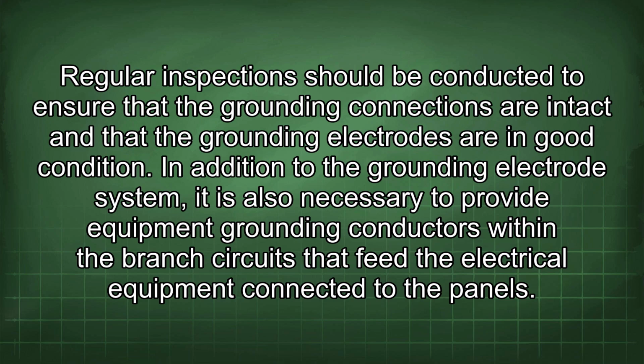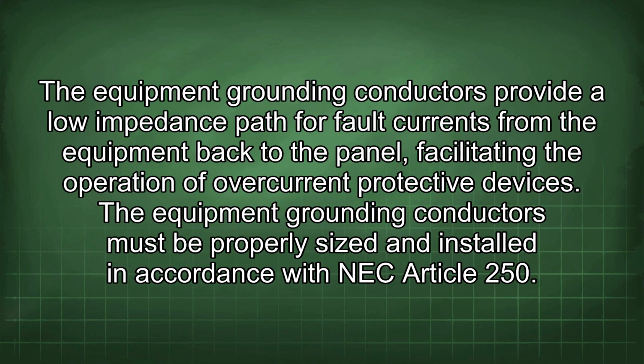In addition to the grounding electrode system, it is also necessary to provide equipment grounding conductors within the branch circuits that feed the electrical equipment connected to the panels. The equipment grounding conductors provide a lower impedance path for fault currents from the equipment back to the panel, facilitating the operation of overcurrent protective devices. The equipment grounding conductors must be properly sized and installed in accordance with NEC Article 250.